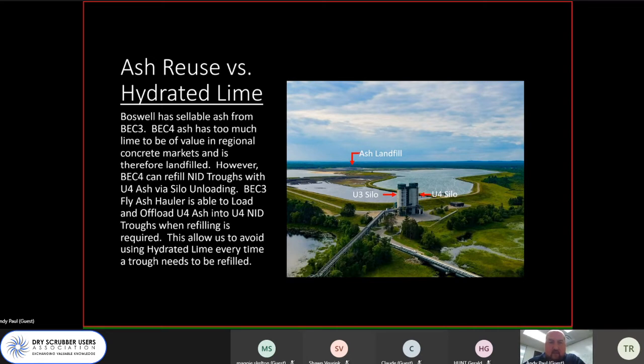Whenever we have to empty out our troughs, like to change a fluidizing cloth in the bottom of the trough, we're able to work with the ash vendor. They can unload from the Unit 4 silo and load that ash back into our troughs, so we're able to reuse our own ash and not have to go out for hydrated lime whenever we have to empty out our troughs.